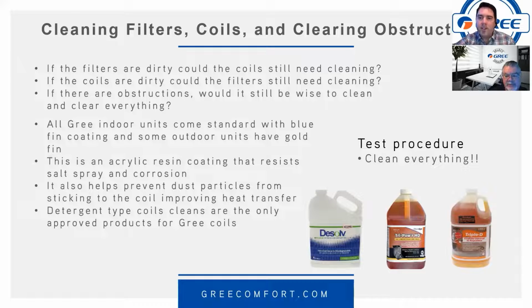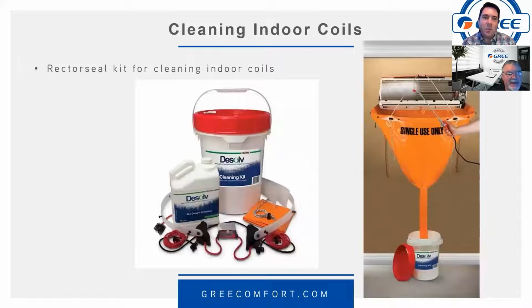Don't forget the blower wheel. And the blower wheel, yeah. Clean that thing off. I'd pull that out of there and take it out and clean it. But this is what the Desolv kit looks like from Rectorseal for cleaning the indoor coils. It's got a bib, and there are some other kits out there similar to this, but the bib helps to contain this runoff down into the bucket, and that's a pretty good tool to keep from making such a mess. Yeah. Either that or take the unit off the wall and take it outside. Yeah, then you're going to charge the system again and all.